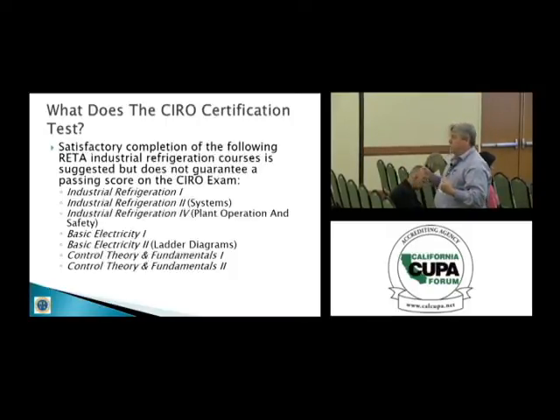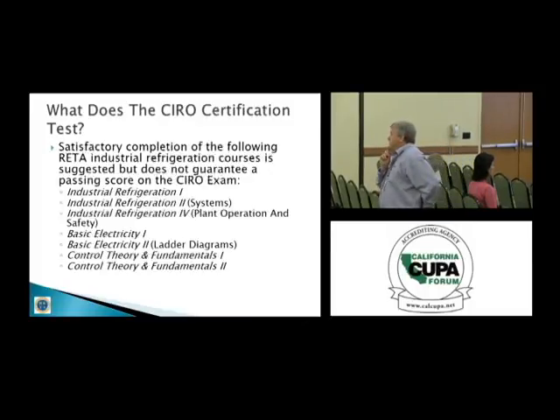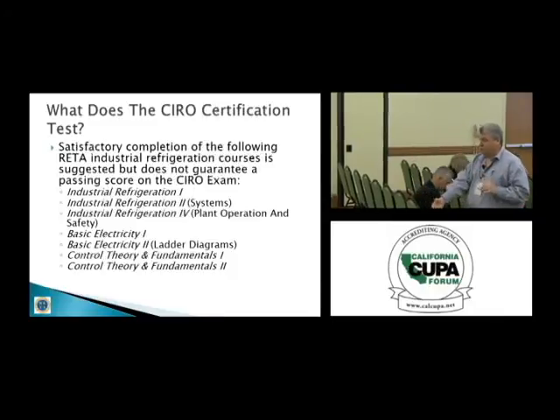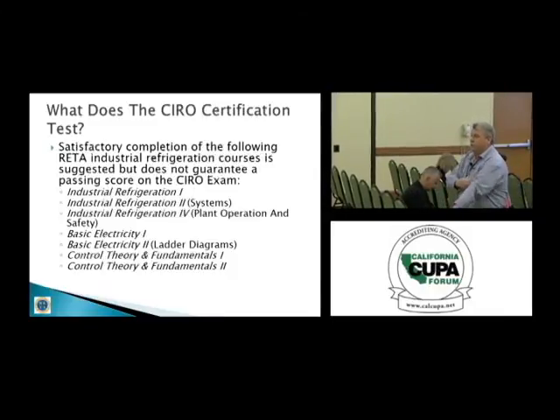If we were in Europe, it would be common to see at the supermarket a refrigeration system sending carbon dioxide out into the supermarket cases, absorbing the heat, bringing it back to a central point, and exchanging that heat to an ammonia system, which then rejects the heat out into the environment. The first system like that in the United States was put into service at the Albertsons store in Carpinteria a few months ago. It has less than 500 pounds of ammonia. It's got reciprocating compressors, and it's got the compressors for the CO2 system. It's standard stuff in Europe. It's new to us.